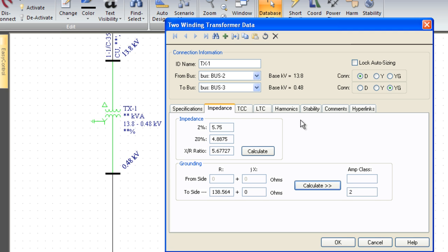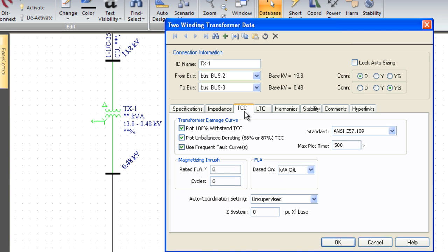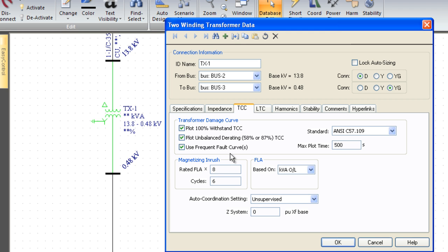If we had a high resistance grounded or low resistance grounded system, we'd just type in the amp class like a 2 amp for a high R ground. It would calculate the grounding resistance and then morph the graphics as we close the dialog box. These other tabs are for more advanced studies such as protective device coordination, load tap changers, harmonics, stability, and things like that. More advanced than what you'd find in a short circuit or arc flash study.